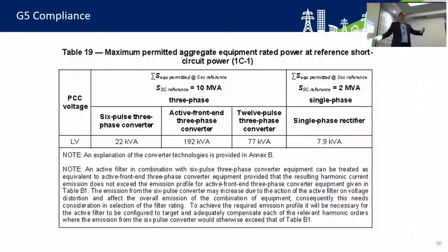We know we can connect 192 kVA at 10 MVA, so then we can do a calculation on the LV network - basically if it's 5 MVA, then you're going to be able to connect half of that, which is 95, 96 kVA. So we pro-rata the calculation, it's a very easy calculation to do, as long as you can provide this information.